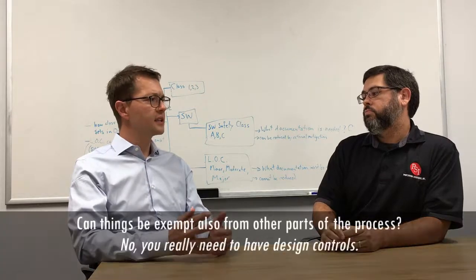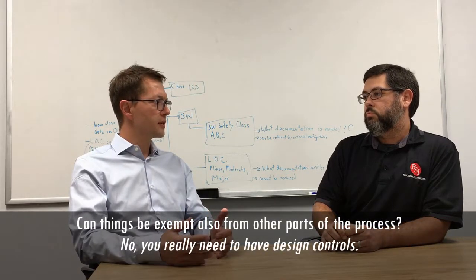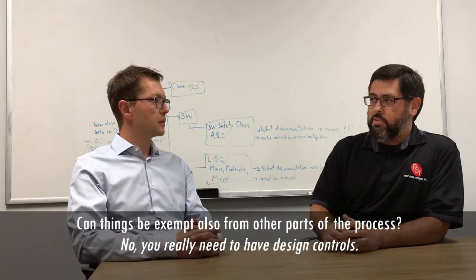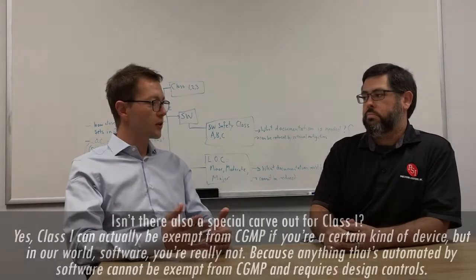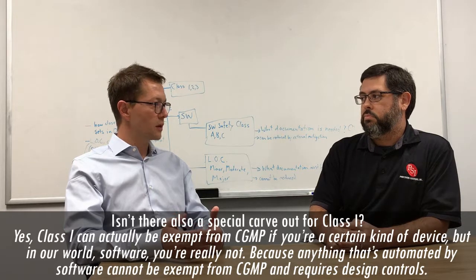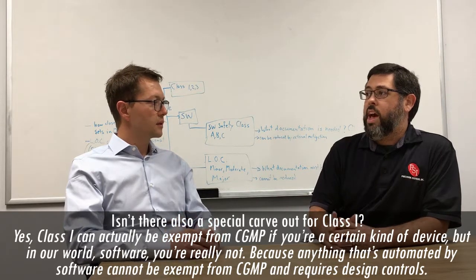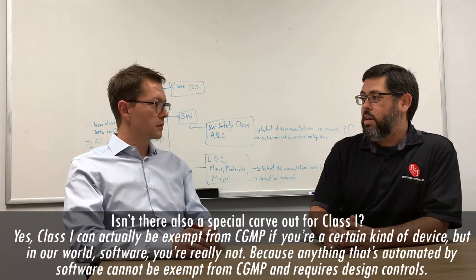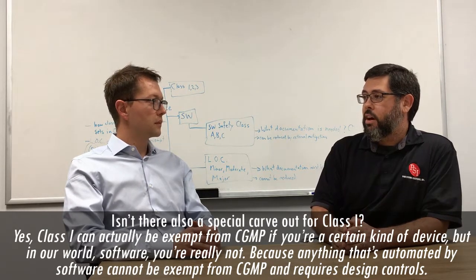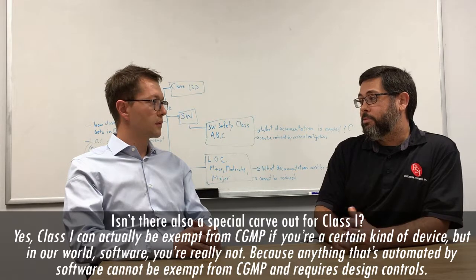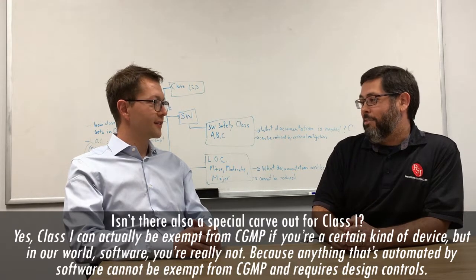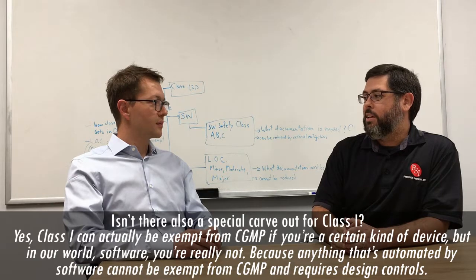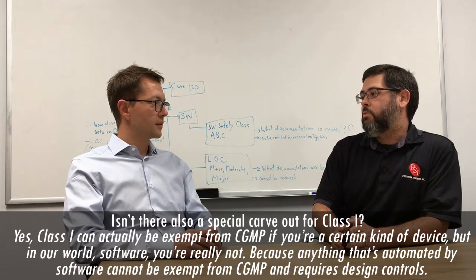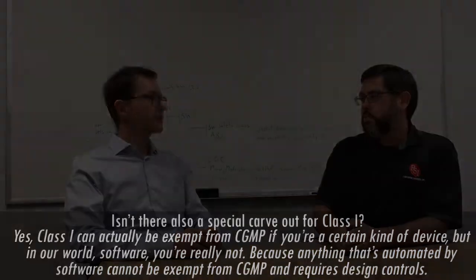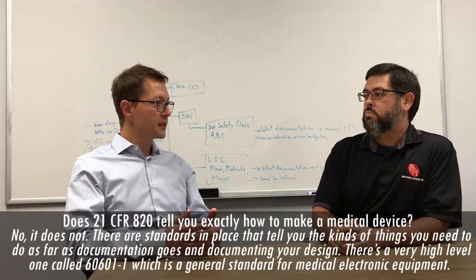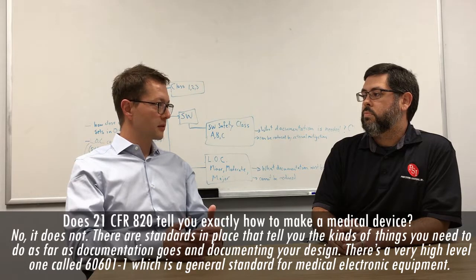So that means like the 510K for the class 2? Right. Can things be exempt also from other parts of the process? No, you need to have design controls. Isn't there also a special carve out for class 1? Yes, class 1 can actually be exempt from CGMP if you're a certain kind of device. But in our world, software, you're really not, because anything that is automated by software cannot be exempt from CGMP and requires design controls.